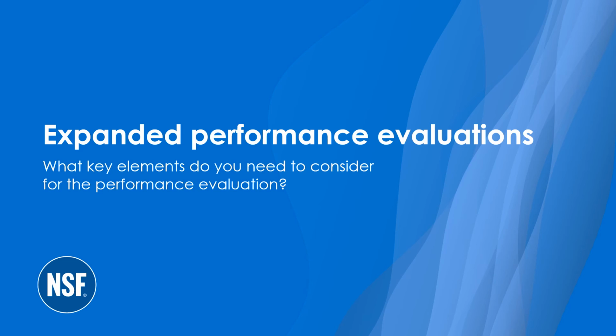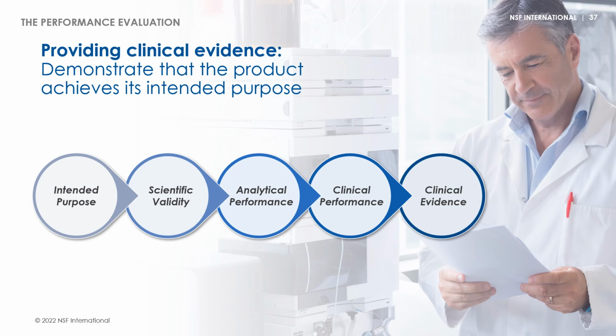In this third part, we will take a closer look at the key elements of the performance evaluation. The performance evaluation for IVDs was already introduced with the IVDD, but has now been much more formalized and specified in the IVDR. The main purpose of the performance evaluation is to provide clinical evidence that the product is capable of achieving its intended purpose. You build clinical evidence with three key elements: a report on scientific validity of your test or instrument, a report in which you demonstrate the IVD's analytical performance, and a report on how the IVD performs with real clinical samples. Now let's have a look at what these key elements may contain.